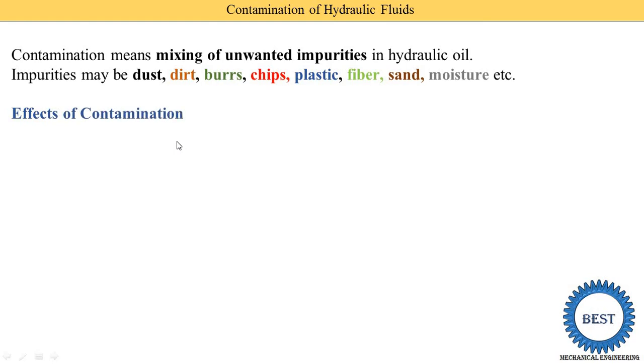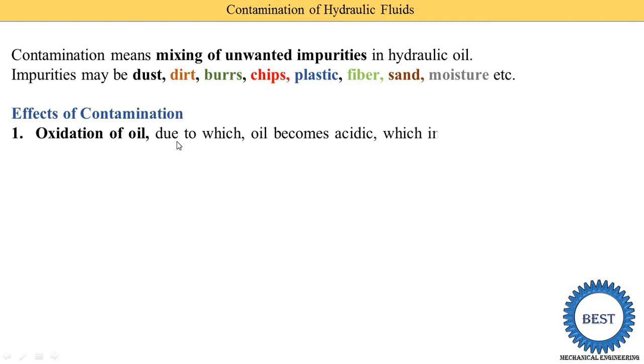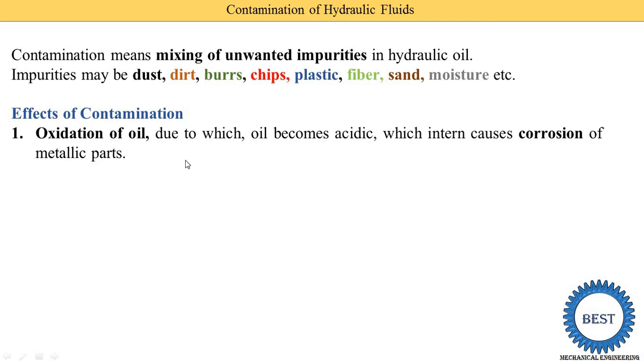The first effect of contamination on hydraulic oil is oxidation of oil, which makes the oil acidic, and this in turn causes corrosion of metallic parts. The unwanted impurities cause the oil to react with oxygen, converting it to an acidic state, and this acidic hydraulic oil corrodes the metallic parts of the hydraulic system.